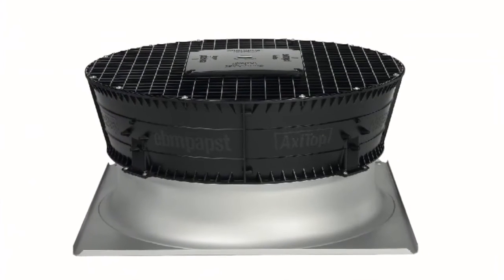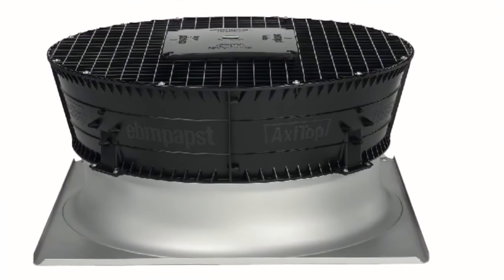As I said before, they are machines designed to have maximum efficiency during the summer period, when the ambient temperature is very high. In winter, this high efficiency enables us to get rid of a significantly larger number of kilowatts than we actually require. Consequently, we are able to adjust the fan's speed and, in turn, conserve electrical energy on the motor, causing them to operate at an extremely low speed and thereby restrict noise while definitely decreasing energy usage.